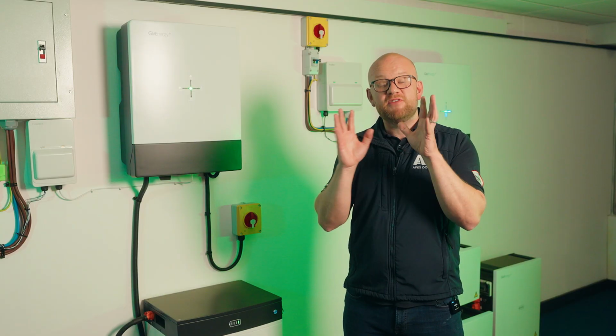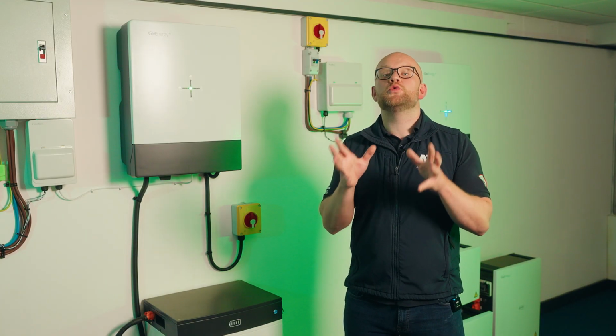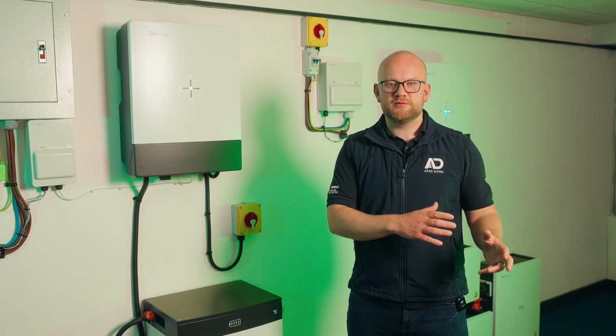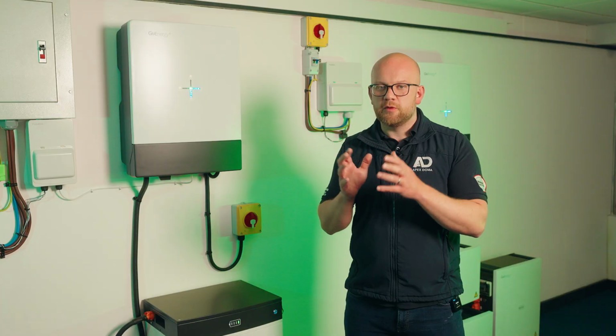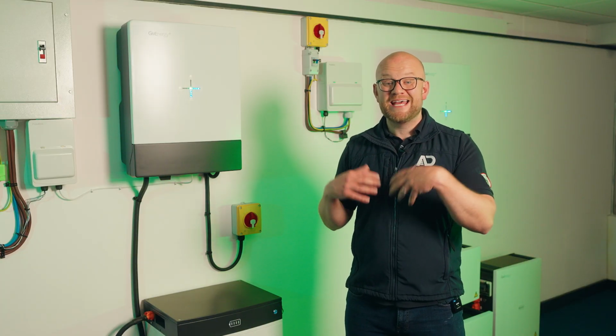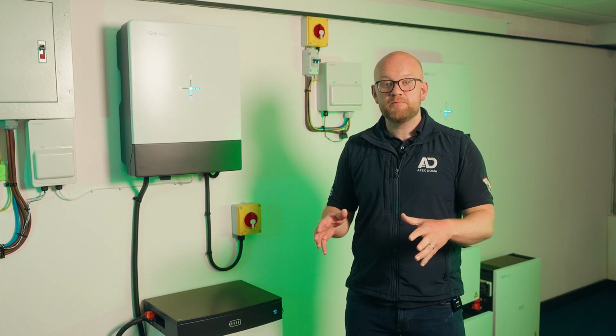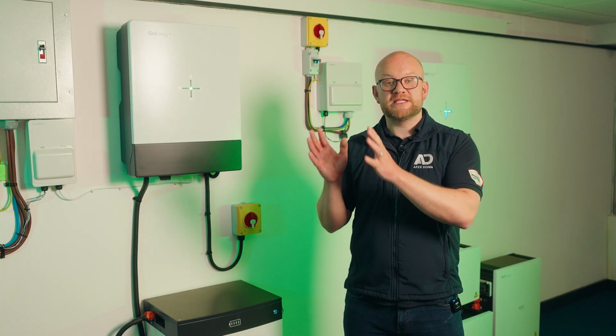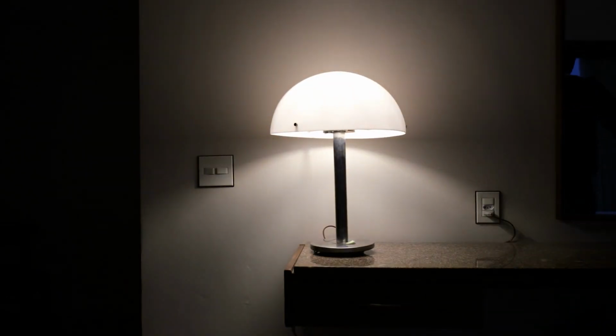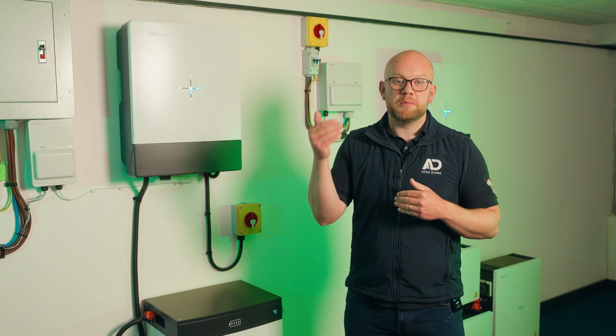Another thing that this hybrid inverter has is a thing called an EPS output, emergency power supply. Now, if it's not set up like this, your inverter will turn off in the event that the power goes off. If it is set up with the EPS enabled, normally you need a fuse board, an earth rod, and a few other little bits as well, like maybe a changeover switch, then effectively, in the event that the power goes down, you can have a couple of options, one of which is an automatic changeover switch. Essentially, if the power goes out, automatically the inverter will change over and you will get a whole home backup, or you can have a manual changeover switch. The power goes out, you turn the switch and the inverter is capable of discharging.